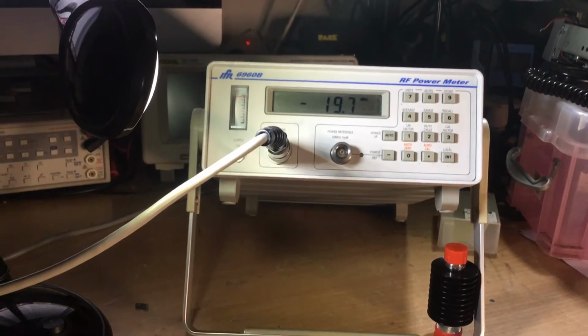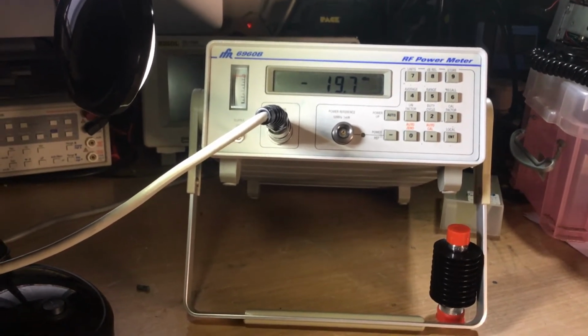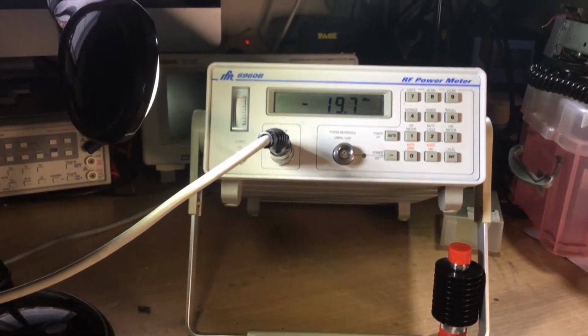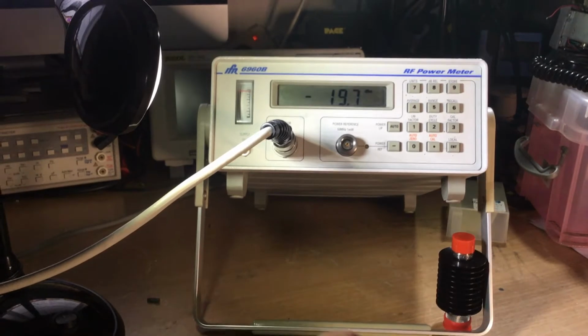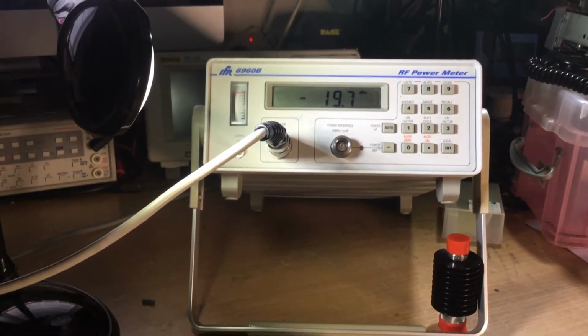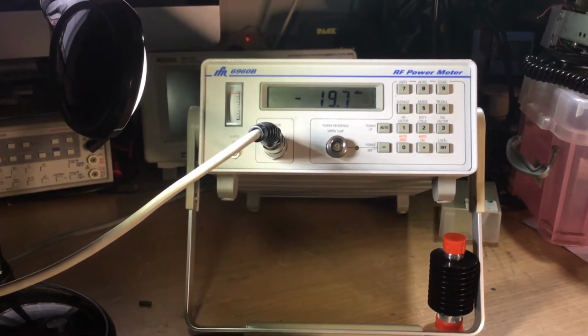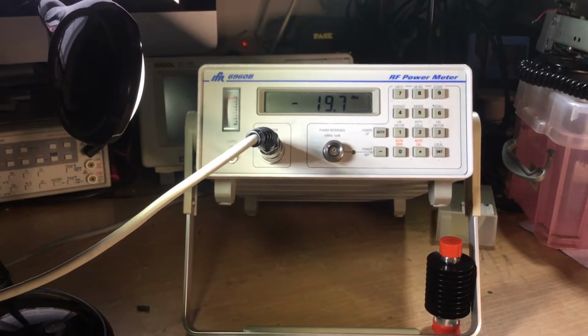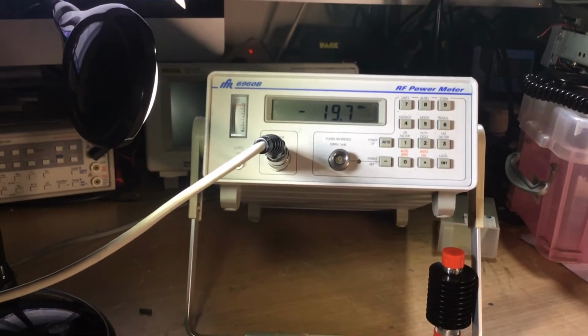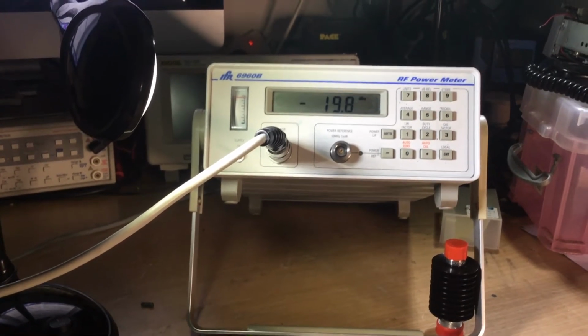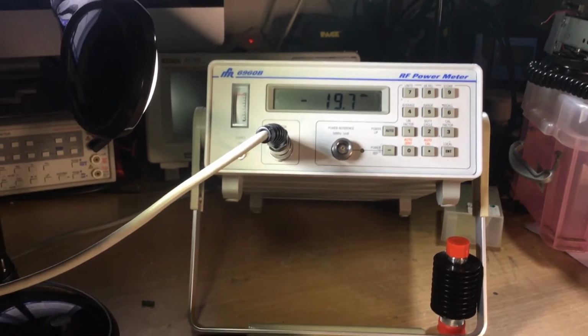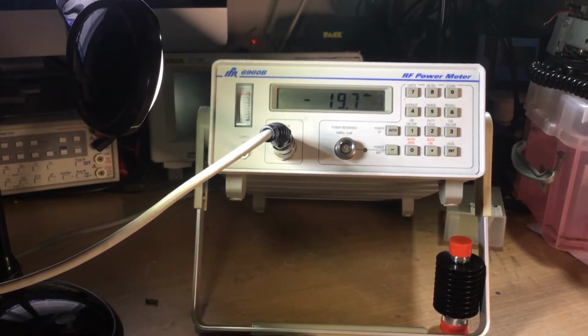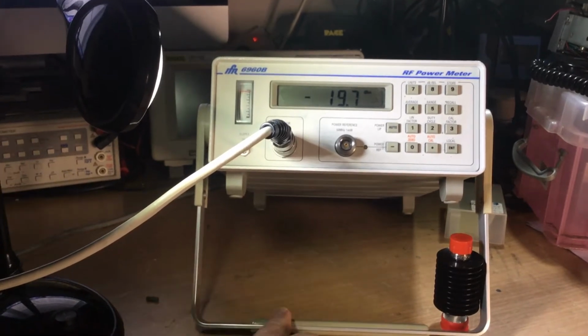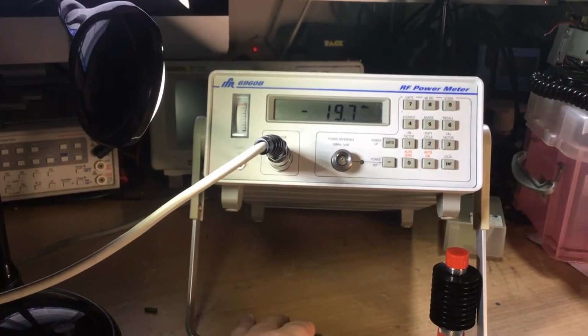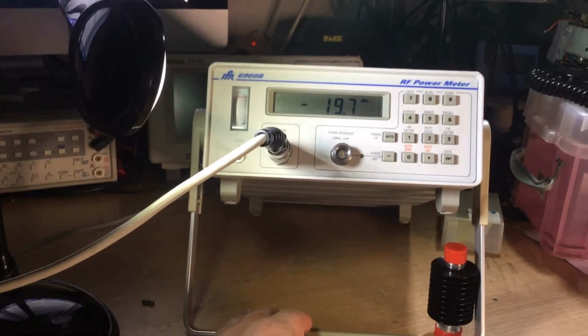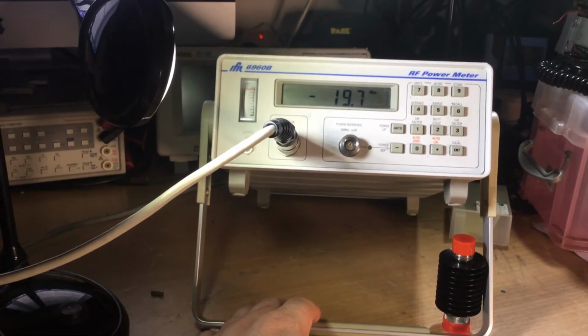So again, that's where these will be used mainly in laboratory environments, or for example production environments, etc. Now for the meter accuracy, the 6960B features an instrumentation accuracy of better than 0.5% in linear mode and 0.02 dB in logarithmic mode. It says a special auto zero circuit digitally stores the zero offset for each of the 5 ranges, thus reducing zero carryover errors to plus or minus 0.03% and providing a zero accuracy of plus or minus 1% of FSD on the most sensitive range for any sensor type.